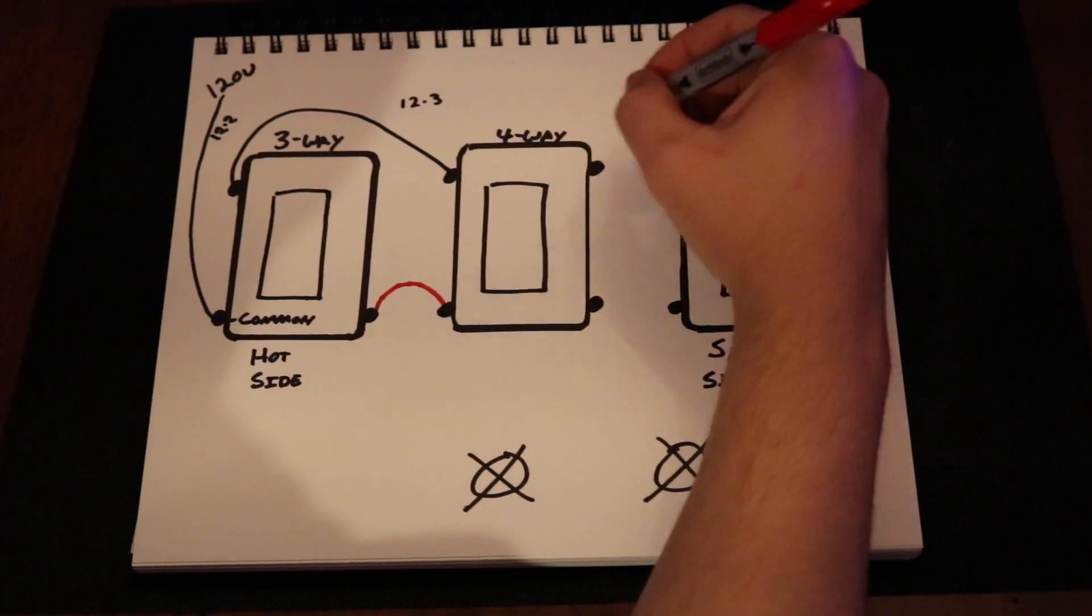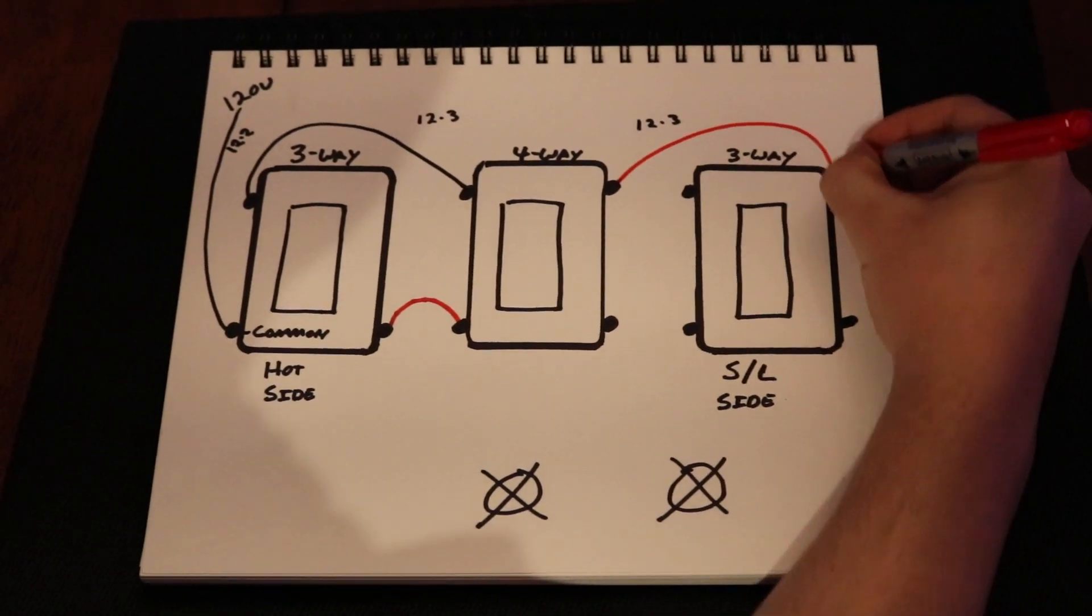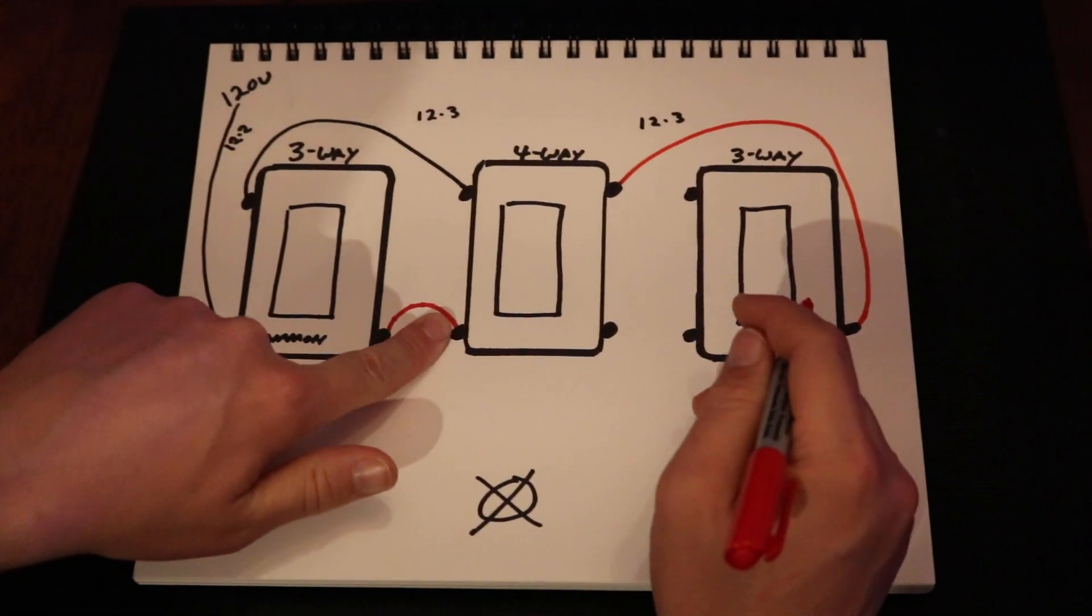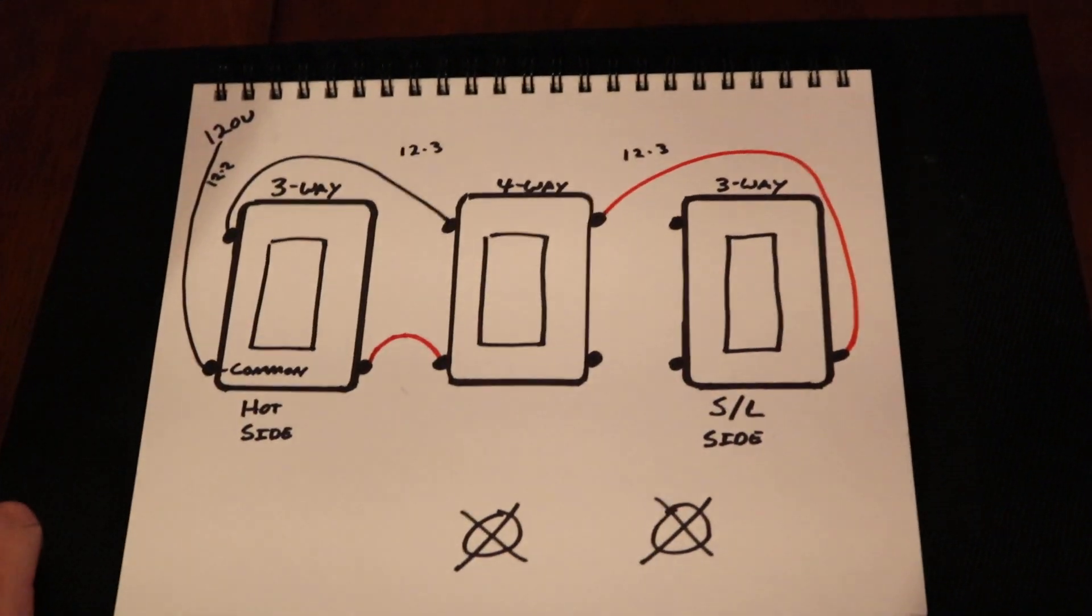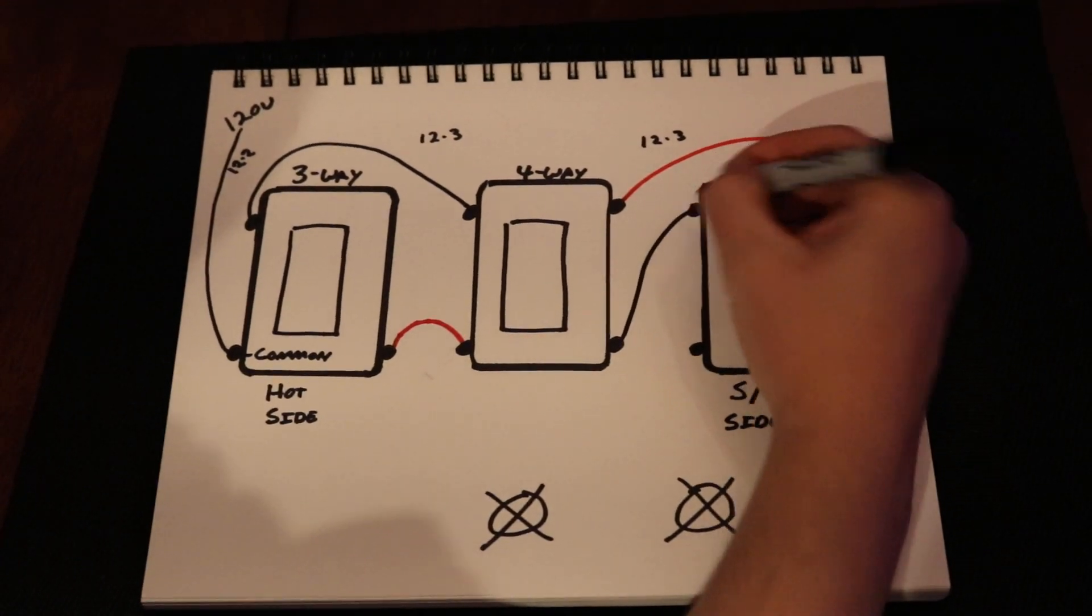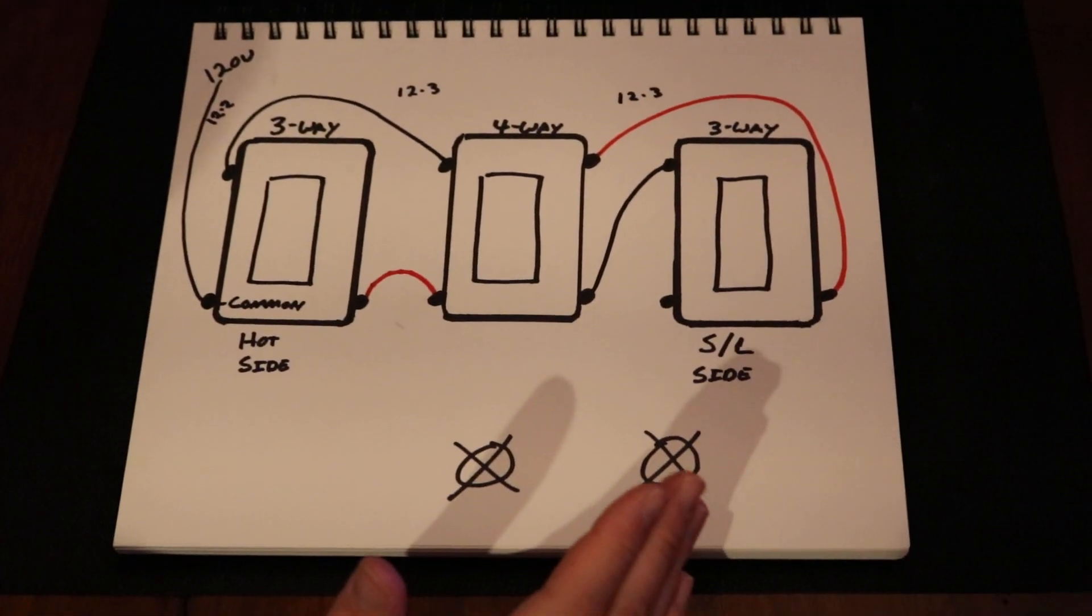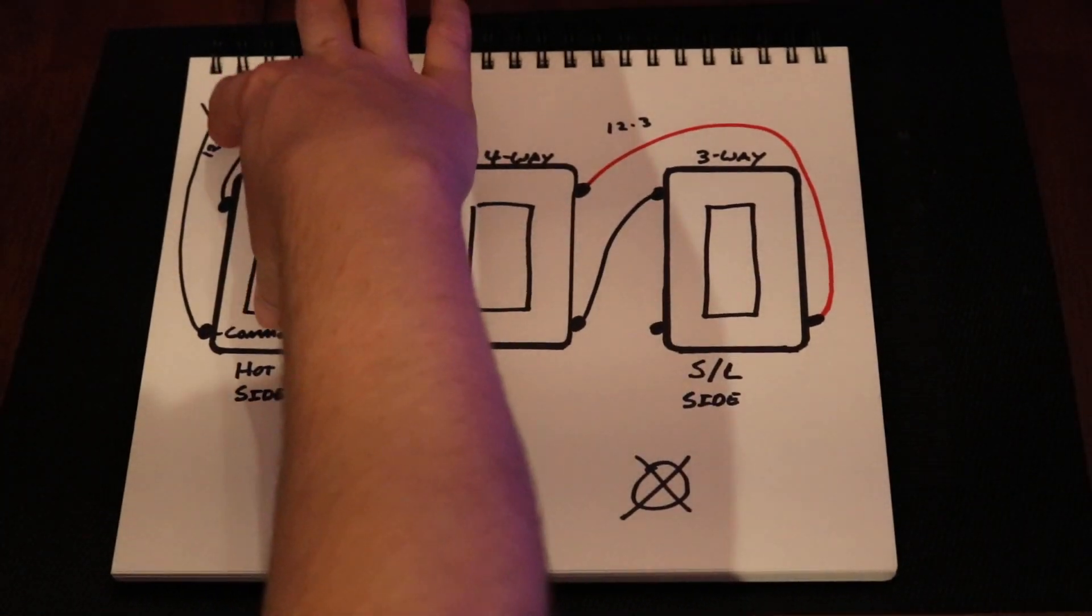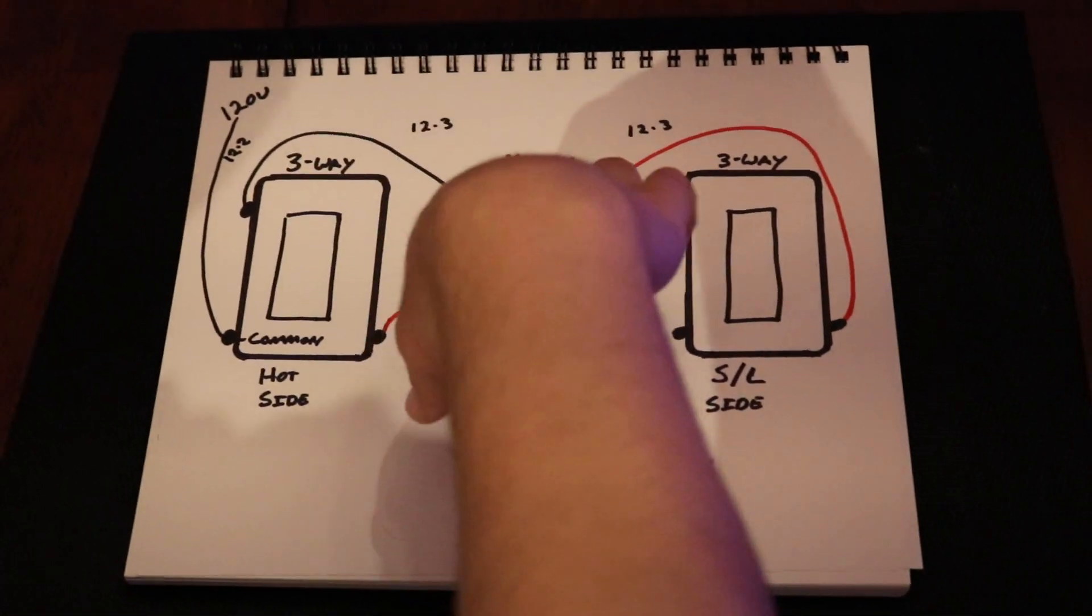You take your outgoing travelers and you put it on the right side, and you crisscross your colors to where you have your red on the bottom left-hand corner on your incoming, on your outgoing you put it on your right top-hand corner, and vice versa for the black. If you wire your four-way switch this way, it'll work every time. You won't have any problems.